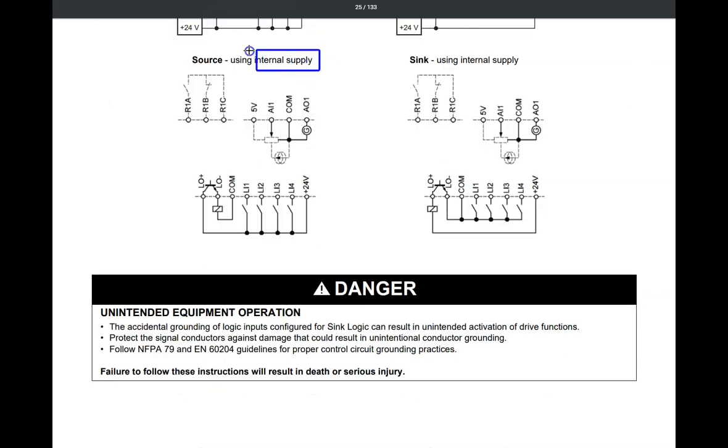If you want to just use the internal power supply that comes with the drive for a local application and you want to use source wiring, you use this diagram for your logic inputs. You take plus 24, you connect to one side of the switch or switches. And when you close the switch, you have 24 volts at that input. And that is a high or run command. You will have to check to make sure that your parameter is set to recognize that.